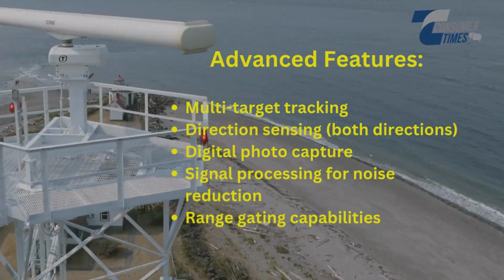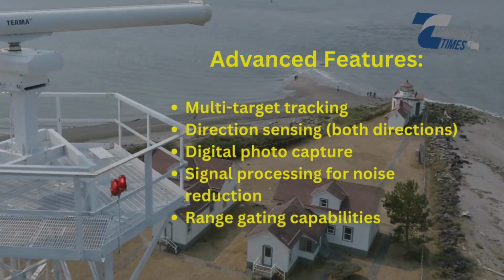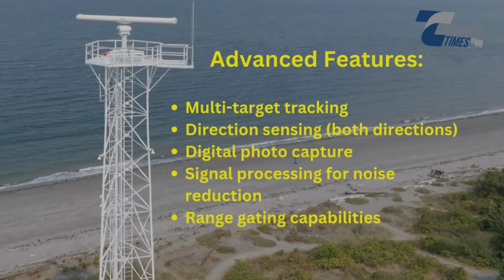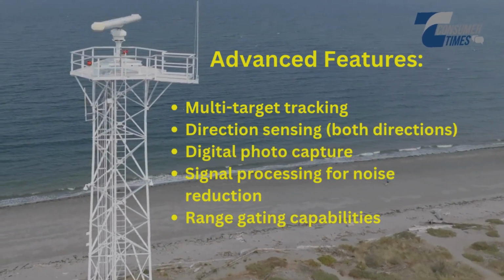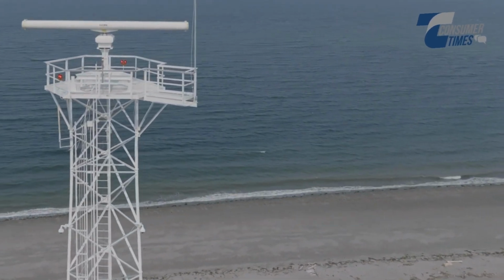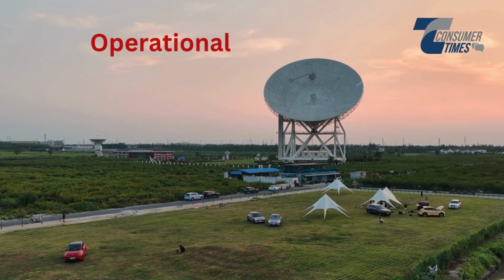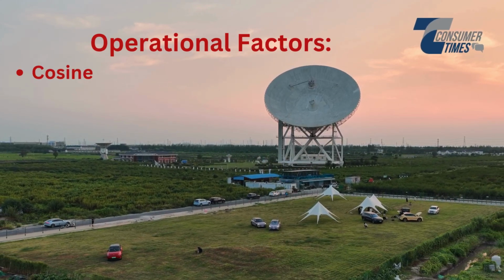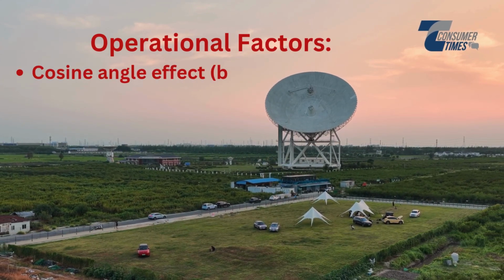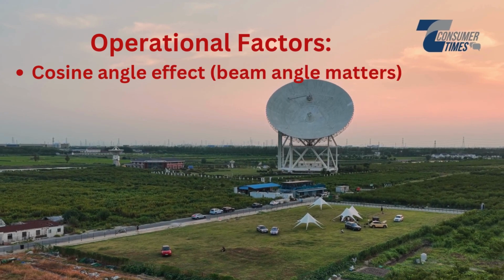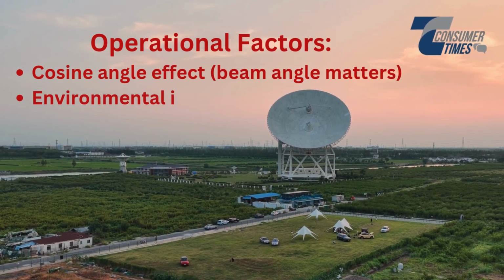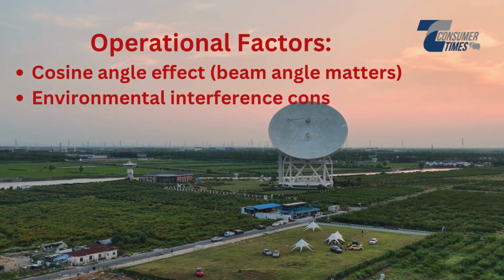Once deployed, individual units require periodic recertification, typically annually, by qualified technicians using traceable calibration standards. This metrological chain ensures that every speed measurement can theoretically be traced back to fundamental physical constants and primary standards maintained by national metrology institutes.